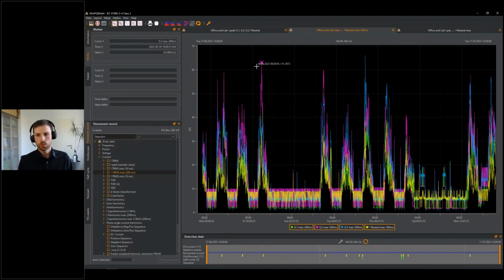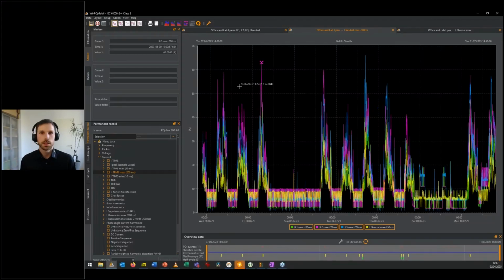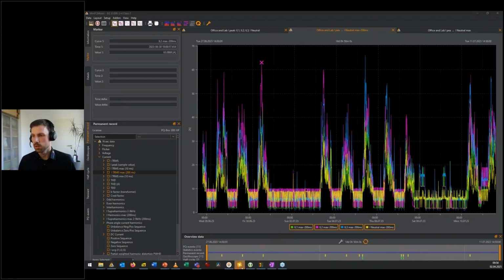So this is something you have to be aware of. Many manufacturers only come up with a 200 millisecond extreme value, minimum or maximum. And this is different from the 10 millisecond values. So you get more extreme of the extreme values from the 10 millisecond values. So you cannot compare these because they are not equal. The 10 millisecond value, if you want to investigate some faults, for example, and want to see what causes these faults, or are there any special conditions in my network, any peaks, the 10 millisecond value is way more interesting.